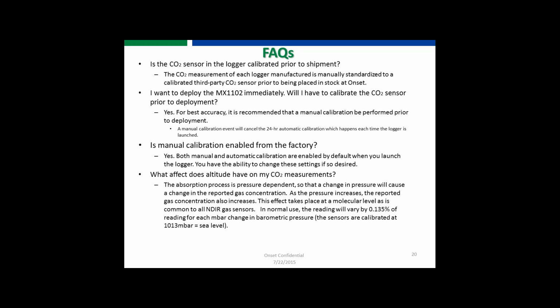Another question that comes up: what effect does altitude have on your CO2 measurements? Very good question. It does. Absolutely. The absorption process that's used in this NDIR sensor is pressure dependent, so it will change. There is a spec here. It says it'll vary 0.135% of reading for each millibar change in barometric pressure.